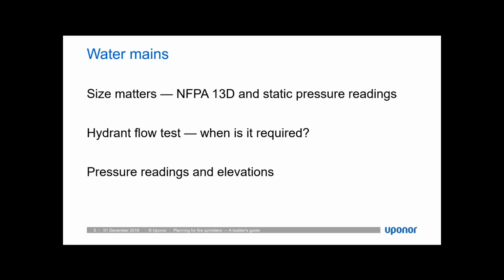It's important to note that pressure readings are dependent on elevation in comparison to the sprinklered home that we are designing. Static pressure will decrease as you move up in elevation, and obviously it will also increase as you move down. So it's important to provide any elevation differences between the point where the pressure was read and the elevation of the home itself. If a site plan showing the water utilities for a sprinkler development is available, it can be extremely useful for your designer or engineer to be able to determine changes in elevation or even identify the potential for different water pressure zones, which is also something that can happen for a larger development. It's not uncommon for a single housing development to have different pressure zones with a pretty distinct dividing line. And it's important for that to be incorporated into the sprinkler design.